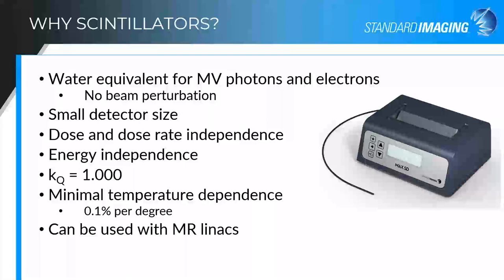They've been shown to be dose and dose rate independent for standard radiotherapy beams, and energy independent as well. The beam quality correction factor of unity really reflects back to the true water equivalence of this detector across the various spectra. So even as your field size decreases, that beam quality correction factor remains one.